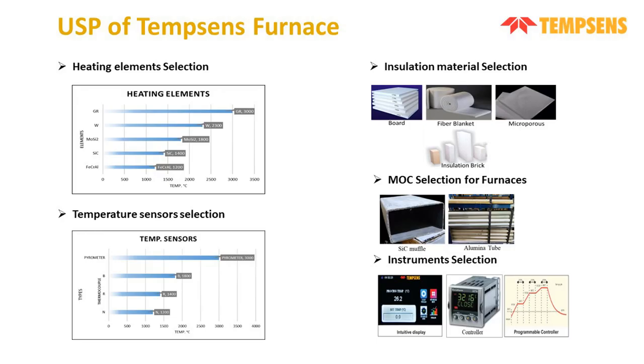Now, coming to the temperature selection, for a different temperature range, we have different thermocouple as well. So, for a range of 1400 degrees Celsius, we use R-type thermocouple, and for a temperature above 1800 or 2000 degrees, mainly we go for pyrometers. It is a non-contact type temperature sensor. Okay. Then the next part of the USPs of Tempsens furnace is a selection of insulation material. So the boards, fire brick and microporous and insulation brick, we combinedly use them to maintain the ambient temperature outside the furnace. So basically we arrange a layer of insulation starting from brick to board to fiber blanket, or from the board to fiber blanket as required.